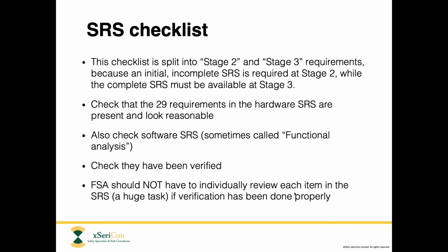By the time we get to stage 3, we want to see that all of the 29 requirements of the standard have been implemented in the SRS, and that the information that's given at least seems to be in a reasonable form. We are not going to check every single item of data to confirm that it's correct. Again, that should be the job of verification. But at least it needs to look like you're on the right track, that you've understood what the requirements are, and that you've written an SRS that is suitable for purpose.